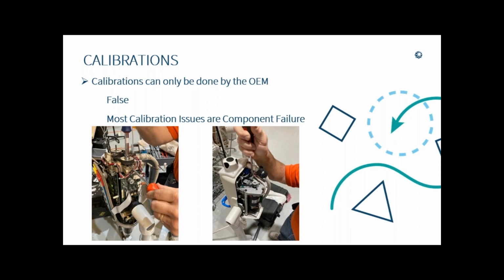What I mean by component failure, let's take the Stellar, that's the most common one out there. The software looks at not only the load cell, but also the amperage going to the motor. So what's going to increase amperage on the motor, to give you an error? Bad motor, bad gears, right? The worm gear runs on bearings. Contrast and saline get down into the bearings and rust them out, increasing the amperage to still provide the program that you have in it. Okay, the load cell and the motor doesn't match up. The amperage on the motor doesn't match up, you get an error. Or the piston goes up and wobbles. It's not running right. It's going to give you that error. It is a component issue.